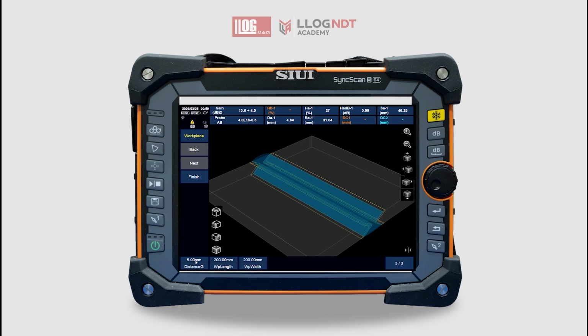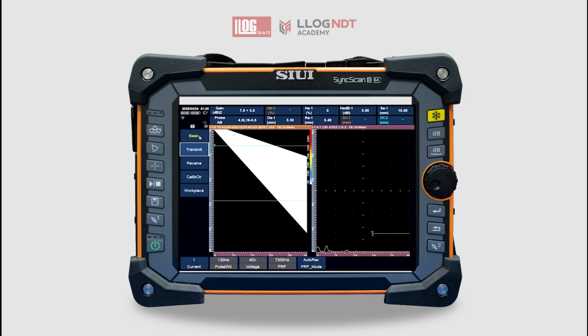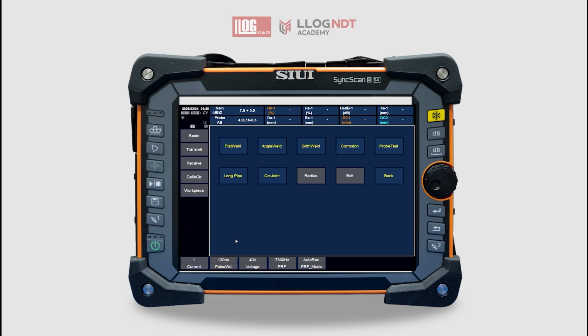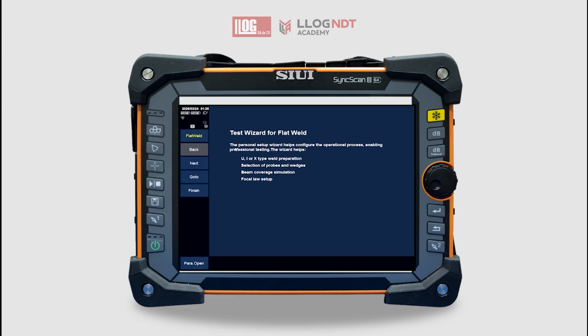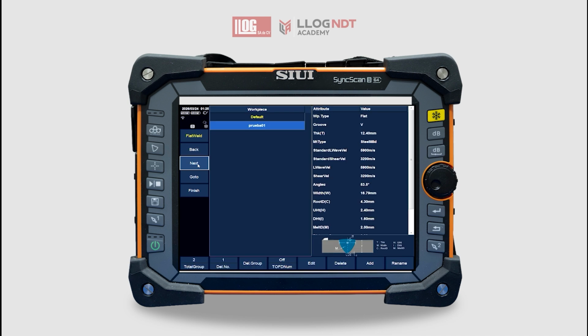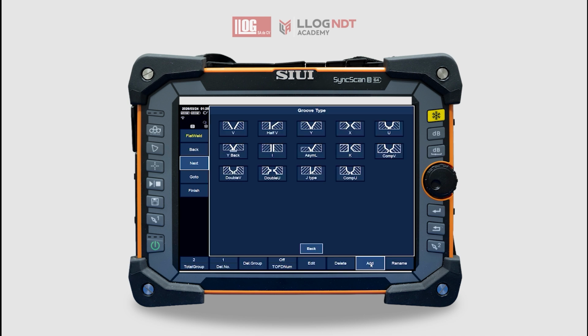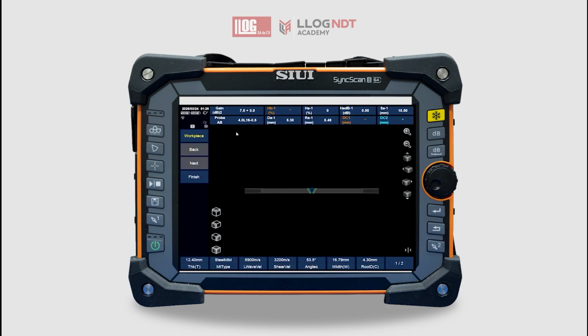Prior to creating the scan plan, we will configure the part to be inspected by accessing the app menu and selecting the joint type. In this example, we select a flat weld and press Next. Now we add a new part and select the corresponding joint preparation type, in this case a V-groove bevel joint, which can be referenced in the Weld WPS. Next, we configure the part dimensions. We set the plate thickness to 12.40 millimeters and select the material as low-carbon steel.